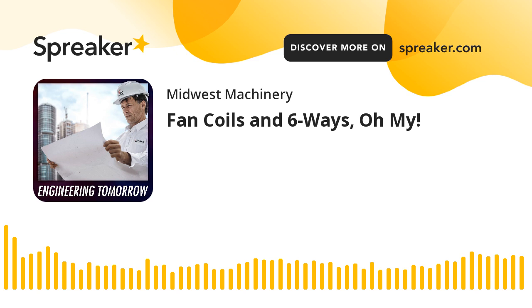Yeah, that's a very good point, because depending on the flow rate or the type of water that's in there could obviously cause major issues with deterioration, with calcium buildup, and thus people will put some type of treatment in their systems to make sure that it flows very evenly, or should I say consistently, through your units. Now, not everybody uses a glycol, and glycol isn't meant for necessarily fouling of pipes, but that's more of a deterrent on low temperatures to make sure your water doesn't freeze in the pipes and then expand the pipes and then cause leakage.